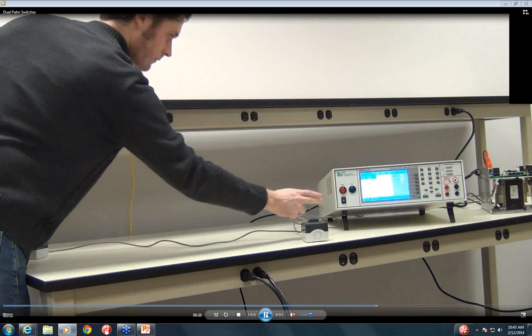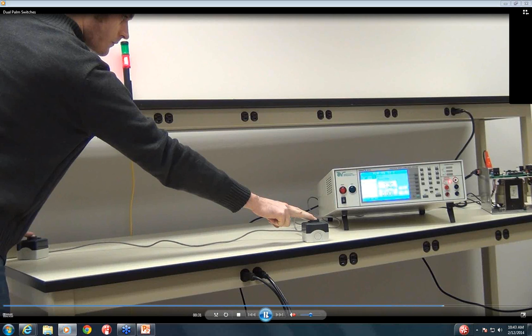Now I'll activate both simultaneously, and it starts. However, as you can see, I lifted one hand while still holding the other, and the HiPot unit screen says abort — I have to keep both hands on the whole time for it to work. So first I'll manually reset. Now I'll hold them both down, and you can see I have to hold them down for the entire duration in order to keep the HiPot test going.